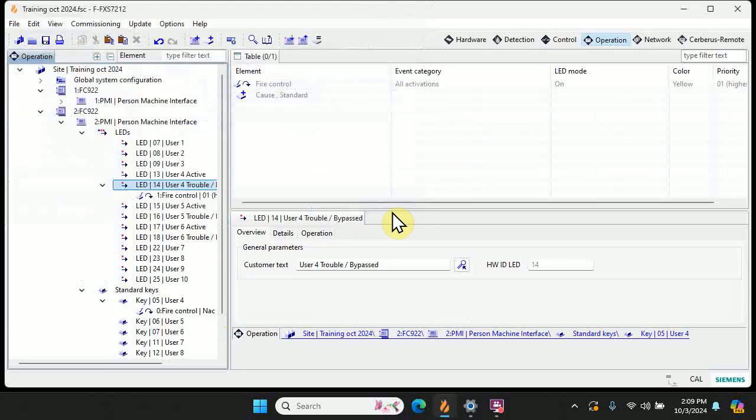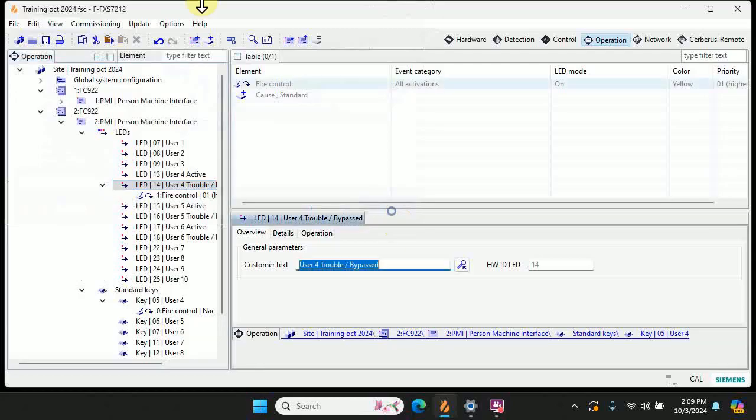All right, with this, now we're ready for 2 panels, both of them having the user 4 button. You press it, it'll ask you for the password. Once you hit the password, the light will come on beside the button and your NAC will be disabled for the entire site. Pressing the button again should do the toggle function, the inversion, which will turn everything back on like normal. And with that, you have been trained on how to make these buttons.